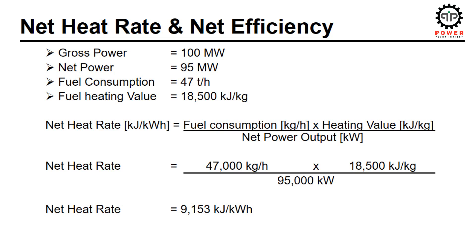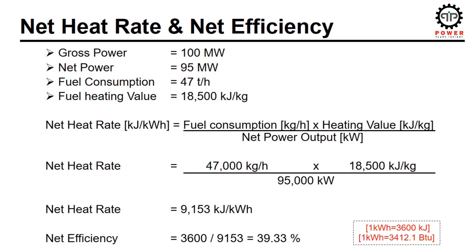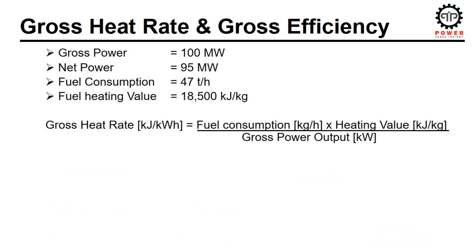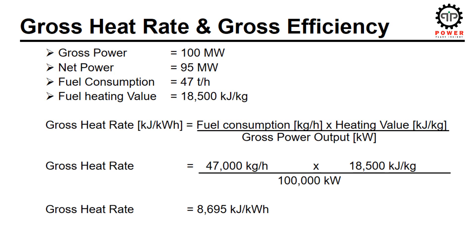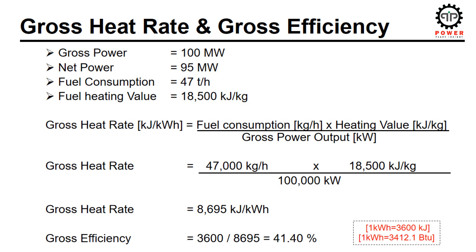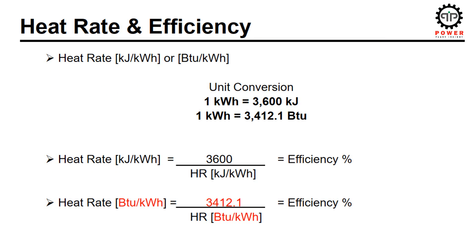For calculating net efficiency, 3600 is divided by the net heat rate of 9153, giving the efficiency number. For calculating gross heat rate, the value of gross power is used in the denominator to get the gross heat rate figure. For gross efficiency, 3600 is again divided by the gross heat rate. In these calculations, 3600 is used because the heat rate units are in SI units — kJ per kWh. If the heat rate were in BTU per kWh, we would use 3412.1 instead of 3600.